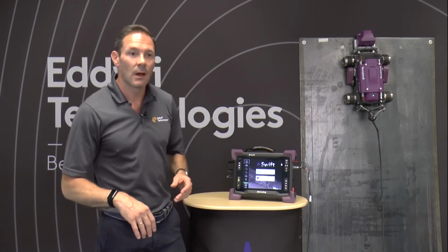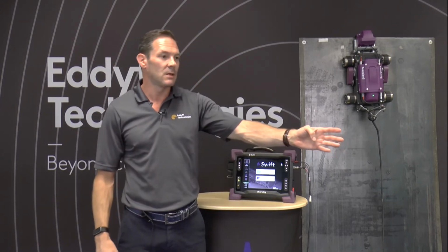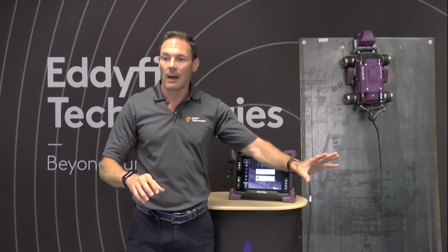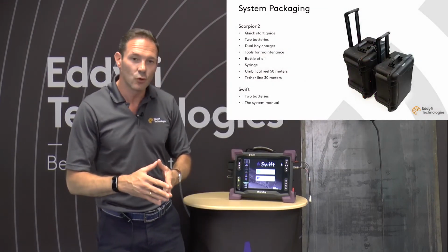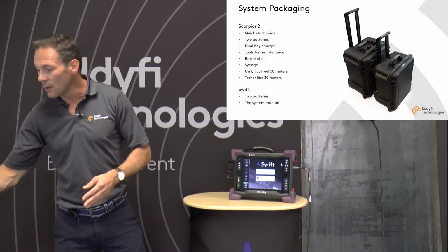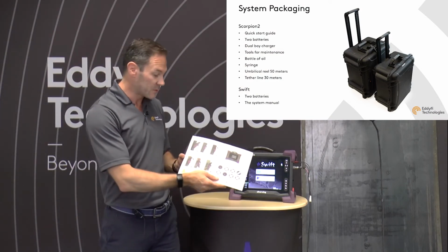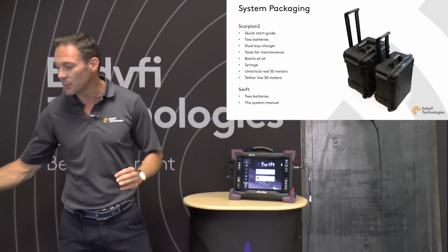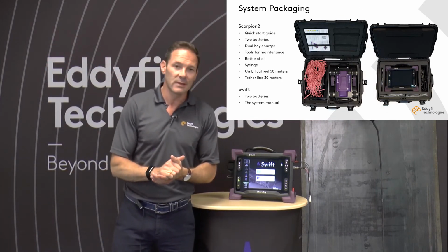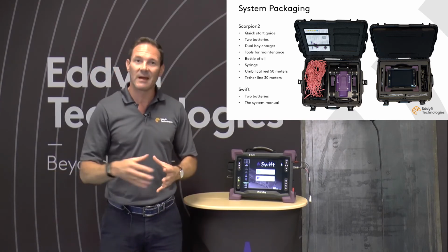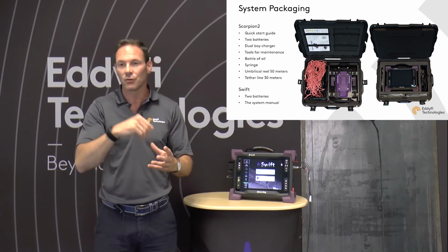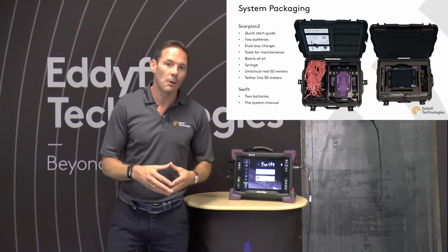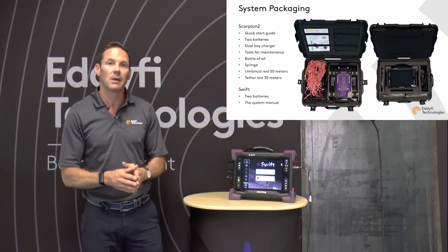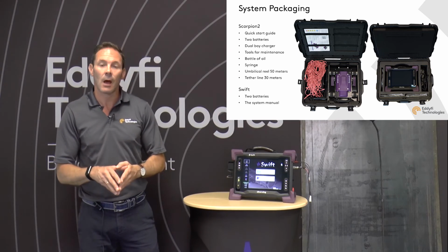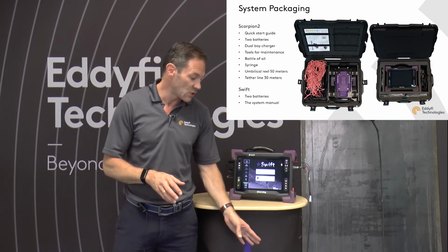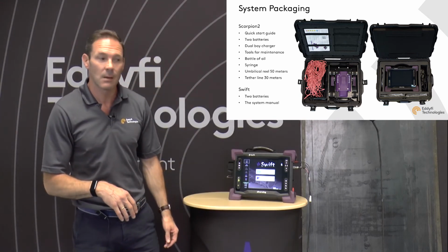For the system packaging we have two separate cases. In one case we have the Scorpion2, in its own case, with a quick start guide to remember the specific details of setting up an inspection. We have two batteries included, a dual bay charger, and all the tools needed for maintenance, such as removing the probe or wear shoes. There's also a bottle of oil and a syringe to keep the probe lubricated, and conveniently placed in the case is a reel with 50 meters of cable and a tether line.